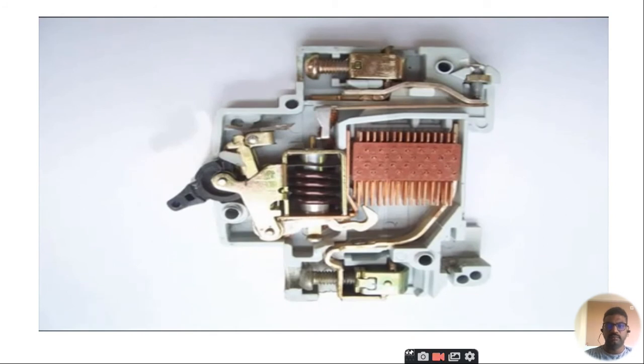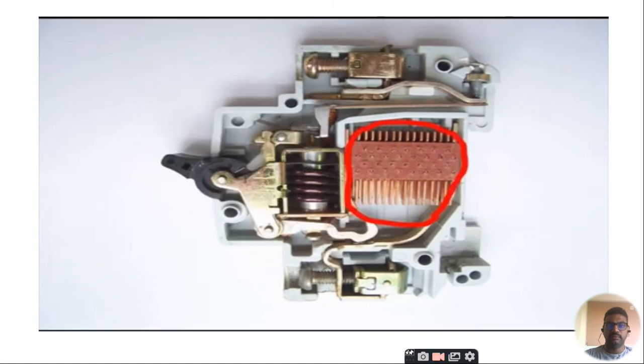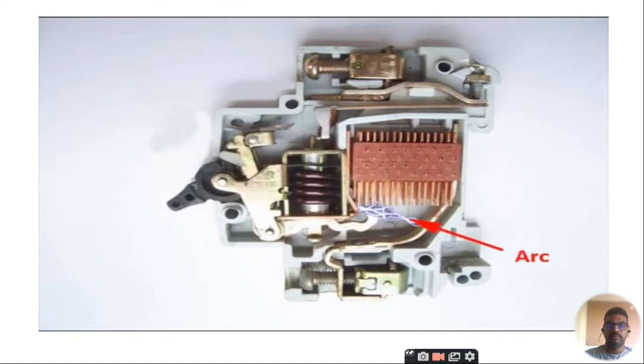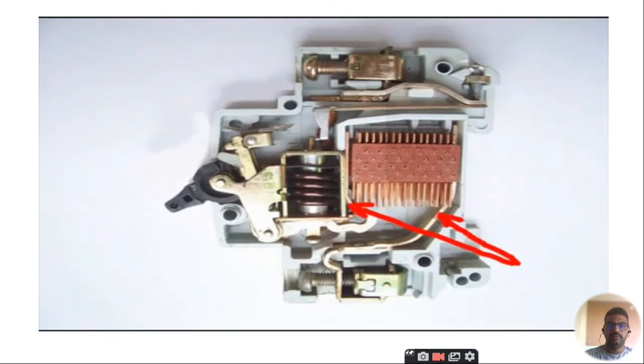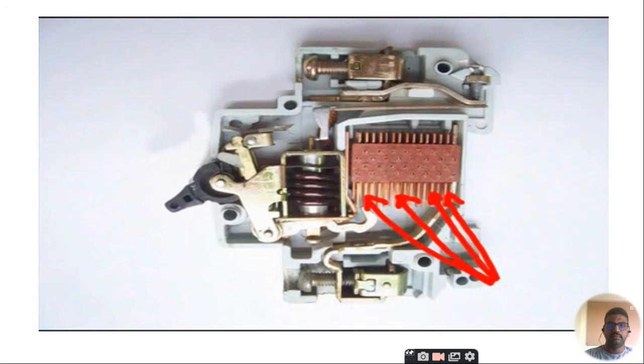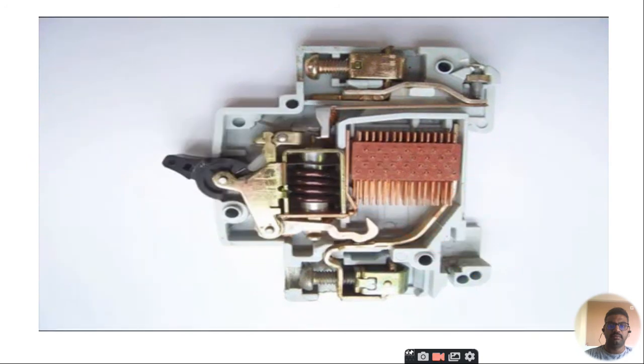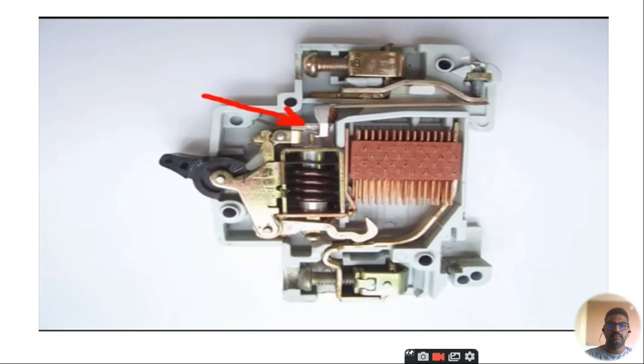A miniature circuit breaker is always provided with arc splitters. During operation of moving and fixed contact, there may be high chance of arc. This arc goes up through the arc runner and enters into arc splitters and is finally quenched. When we switch on an MCB, we actually reset the displaced operating latch to its previous on position. Thank you.